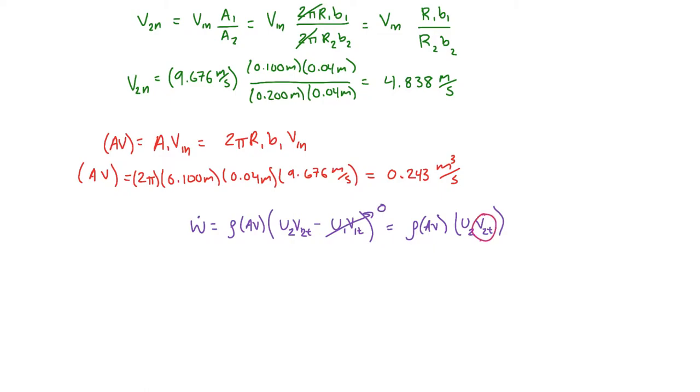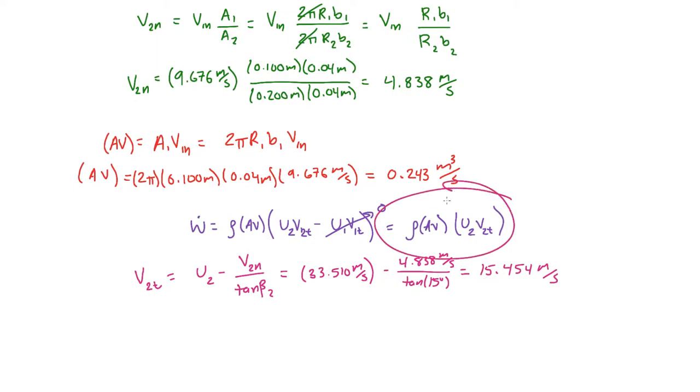I forgot to actually define another velocity. That is the tangential velocity at 2. But we have the normal velocity at 2. So we should be able to find that quite easily. The tangential velocity at 2 is simply u2 minus v2 normal over the tangent of beta 2. That ends up being 15.454 meters per second. So now we have everything for this equation to find the power of the pump.